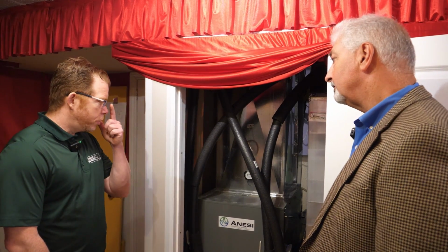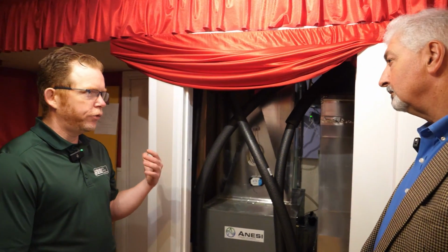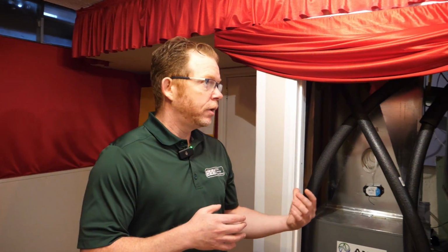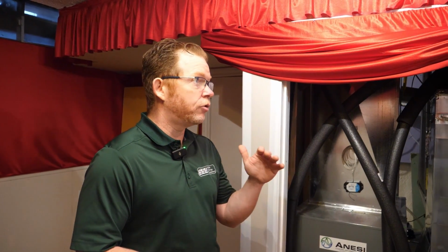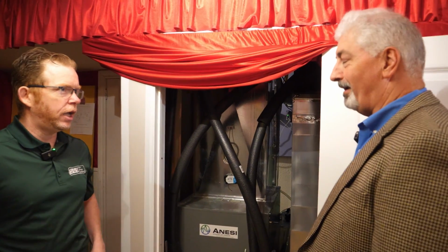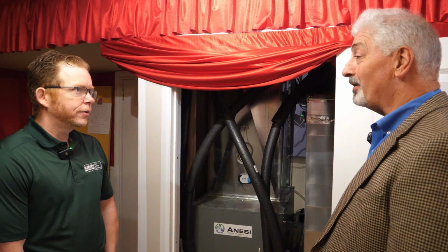Yeah, I think one of the important things, and it doesn't really come into play here, but we'll say it since we're talking about it, one of the things we see happen commonly is people will take a heat pump technology and they'll apply a traditional indirect on it, which is where you're going with this. Traditional indirects do not have a lot of surface area inside of them, so you don't get great heat transfer. On a heat pump, at least an electric heat pump, we want to have an indirect that's got a very large surface area on the coil. It sounds like you're saying something similar with yours, like please don't go and buy any old indirect off the wall. Yeah, I'm saying actually the exact same thing.